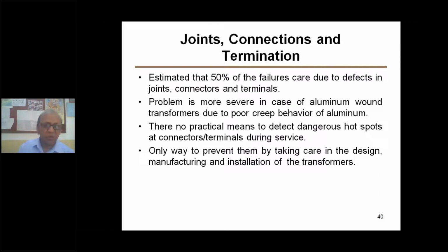The problem is most severe in the case of aluminum wound transformers, due to the poor creep behavior of aluminum, which is already emphasized. There is no practical means to determine the hot spot in the terminals and the windings. Especially for distribution transformers, we can't provide sensors for this purpose. Somewhere a hot spot is appearing in some corner, so you can't measure all the time. It may appear during service, when creep has appeared. It can only be prevented by taking care in design, manufacturing and installation of the transformer, with proper connections and proper joints, so that local hot spots can be avoided.